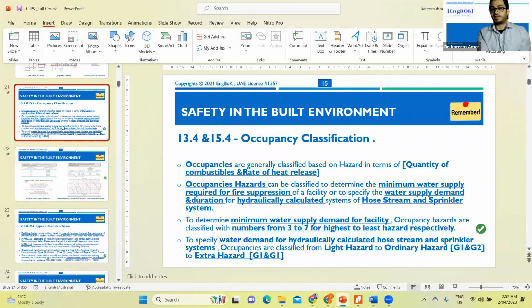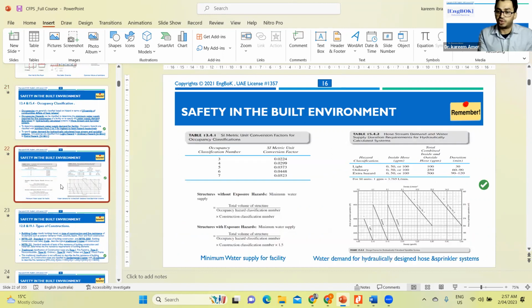Then we focus on occupancy classification, section number 13 chapter number 4, section number 15 chapter number 4: light, ordinary, and extra hazard. You should understand how to calculate water demand for a sprinkler system or for the standpipe and hose hydraulically, not just using pipe schedule — we care about hydraulic calculation.